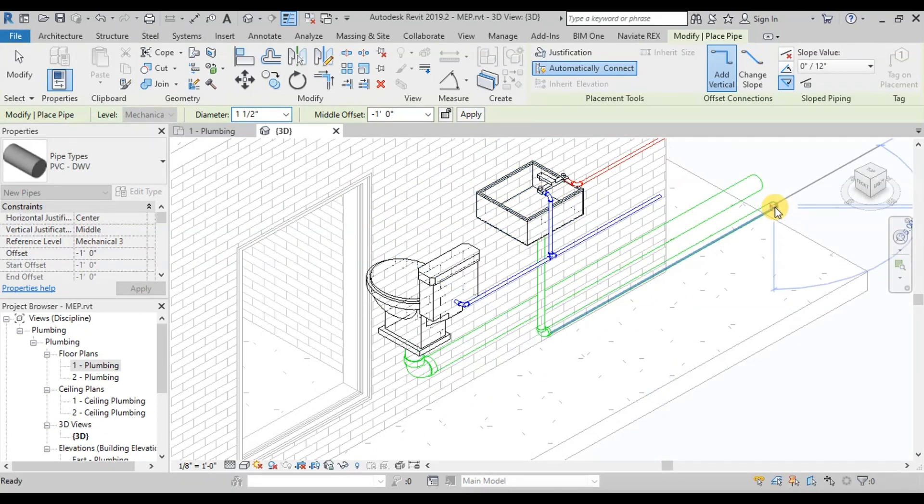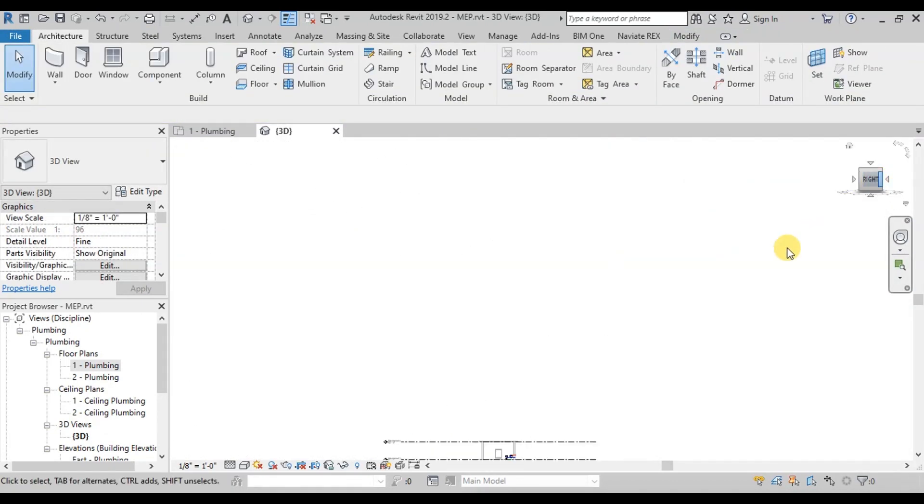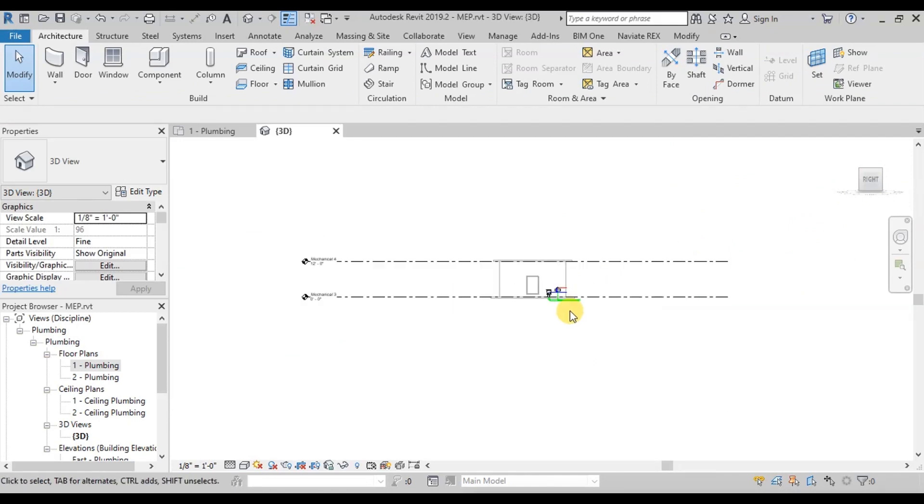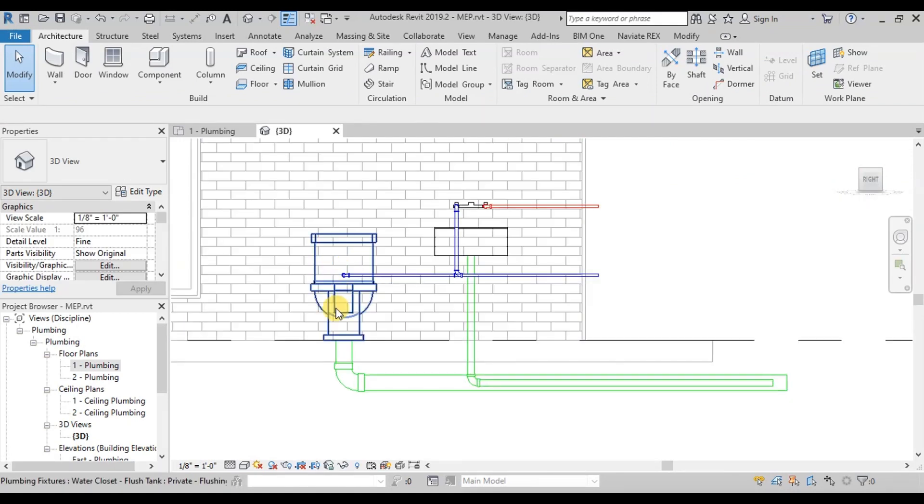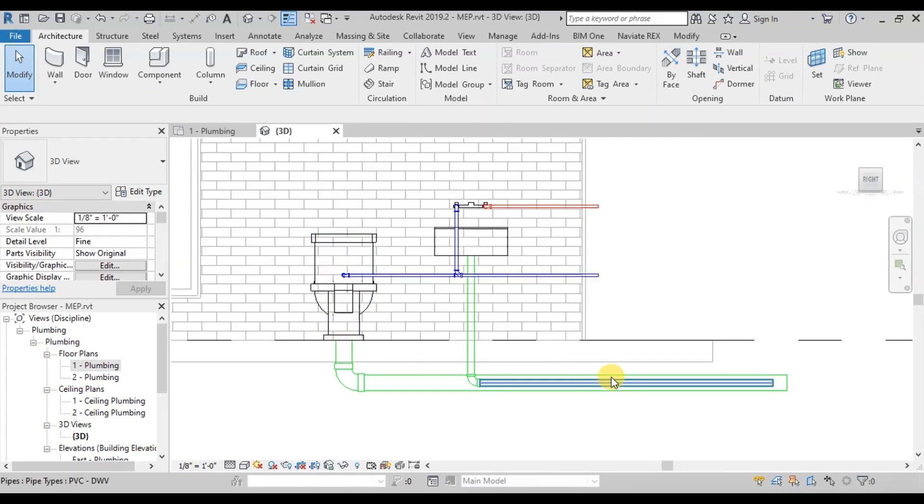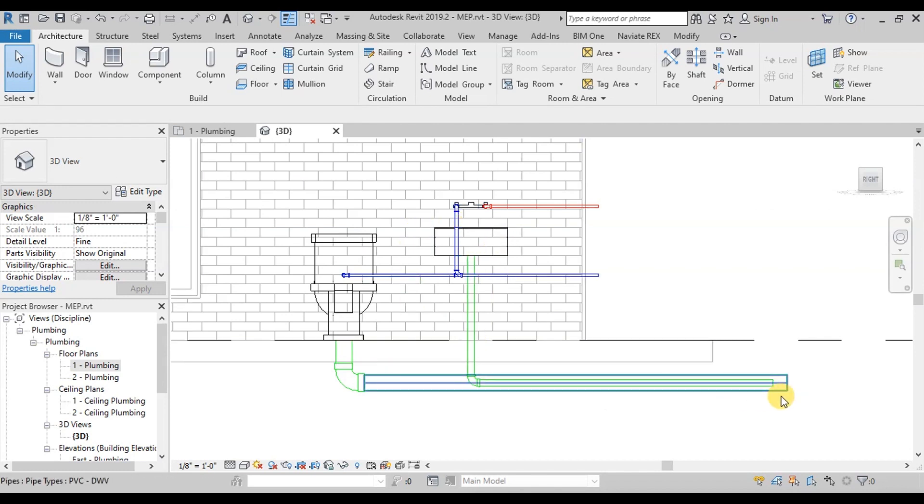We will change the 3D view to elevation view to see how this pipeline is drawn. For Sewage, 4-inch pipeline is going outside of the building. For Waste Water, 1 and a half-inch pipeline is used.